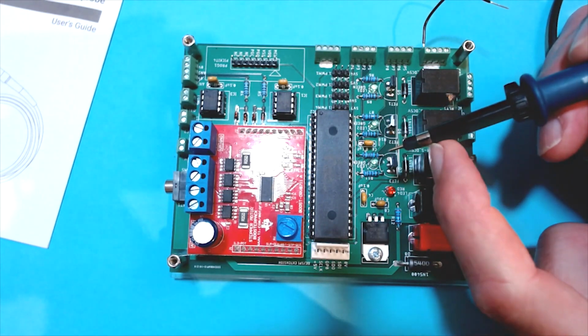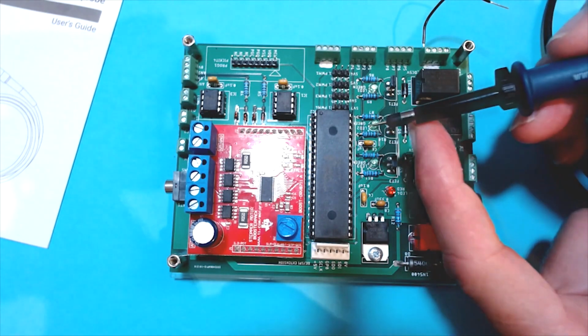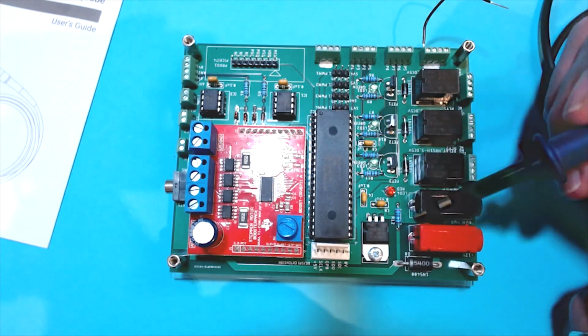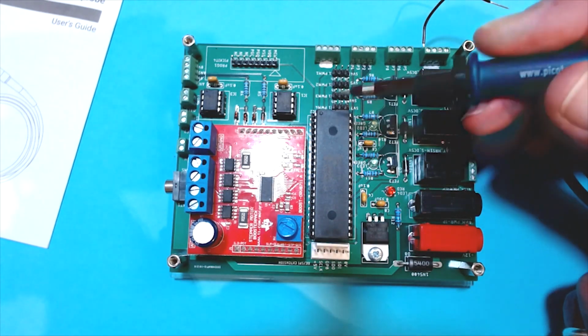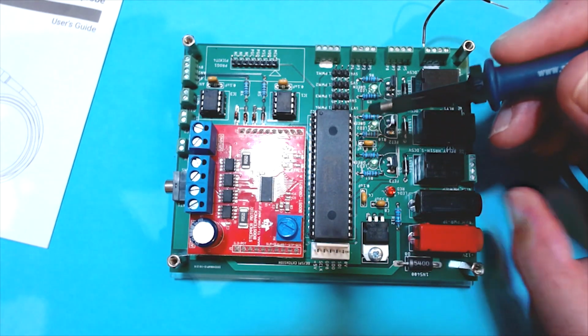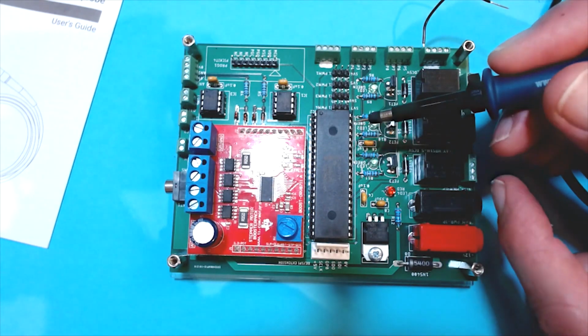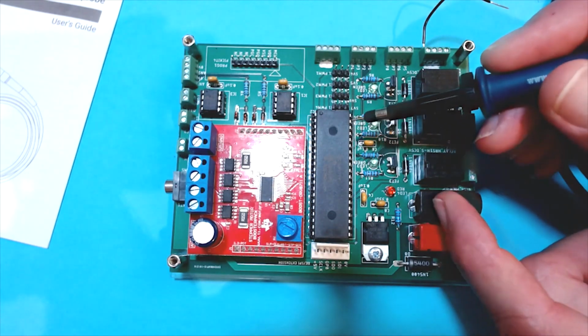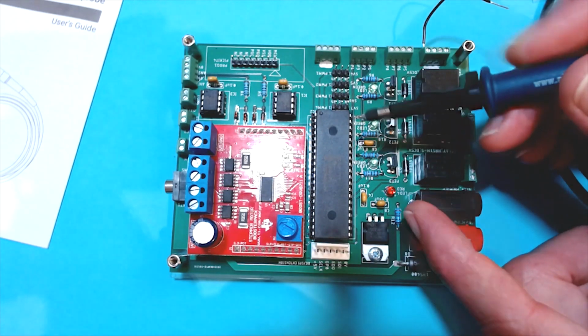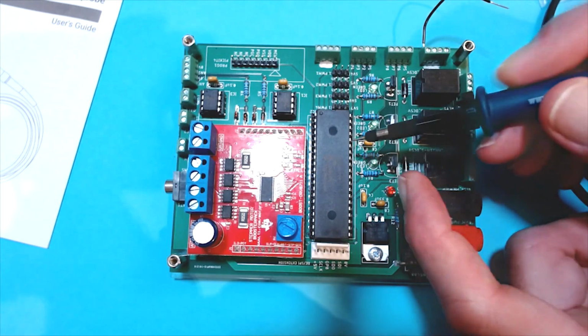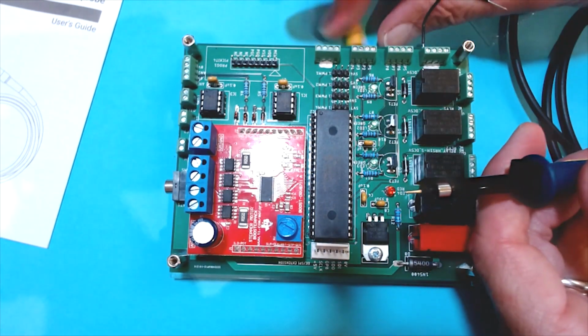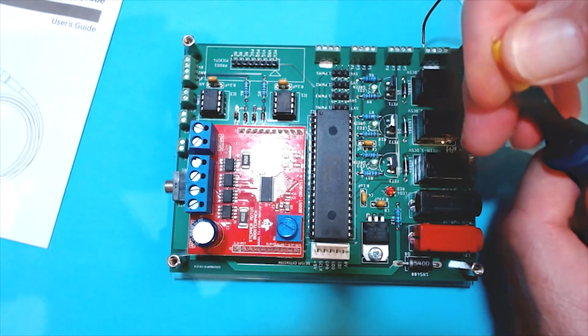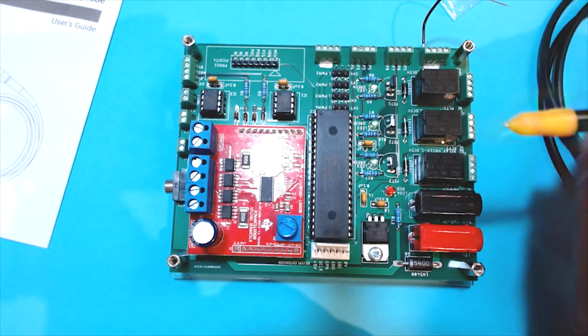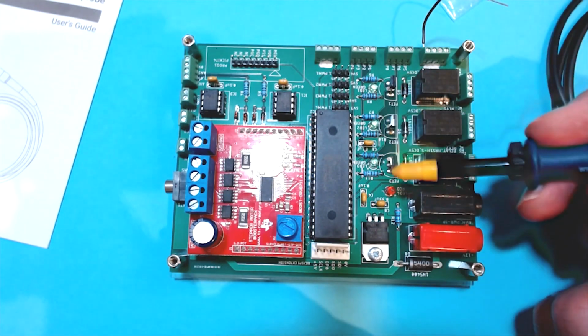When you've got this whole scope probe connected to ground, you can accidentally touch this sleeve on your electronics. This is particularly a problem if you've got power transistors or power MOSFETs, where the tabs are not necessarily at 0 volt potential, which is generally the case. You can end up blowing your circuits because this guard ring has touched some of your electronics. So the best thing to do is make sure you always have your locating sleeve on like this. This is just one of the two variants of the locating sleeve, and it protects the guard ring to make sure it doesn't touch any of your other electronics.